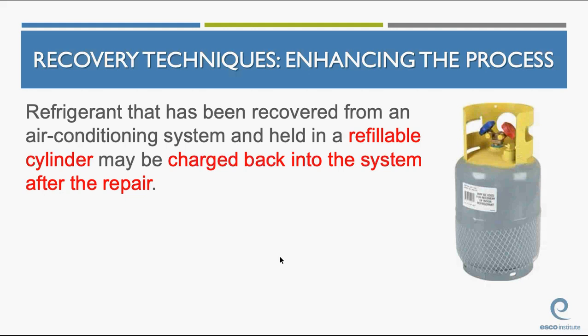If the compressor was burned out or it's contaminated with other refrigerant. Yeah, if I have any contamination, any acid, any compressor burnout, I definitely want to replace that refrigerant. I don't want to take a chance, because if there's acid in it, that new compressor might have a lifespan of a year.